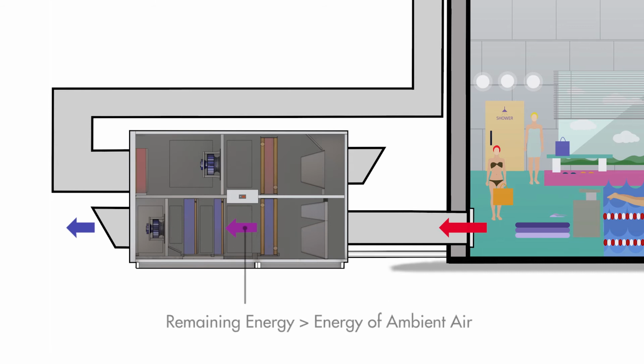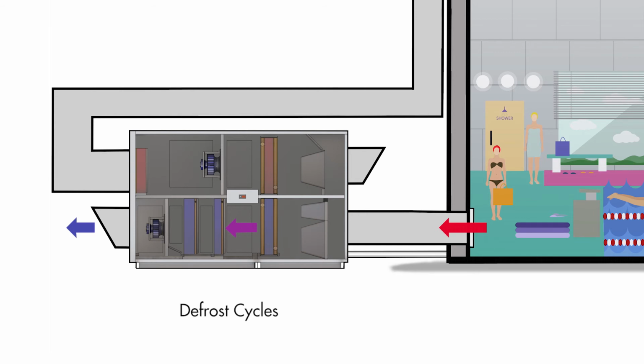This presumes that the remaining energy in the exhaust air is greater than that of the ambient air, but this is true for much of the year where heated pools are generally located in Australia. Further, by placing the evaporators in the exhaust air, the need for defrost cycles is eliminated in most cases, with the warmer exhaust air not being cooled low enough to produce ice in the coils.